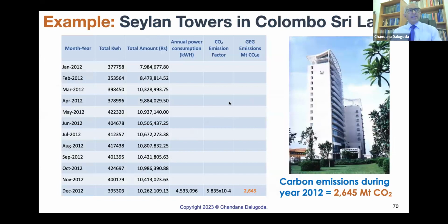Seylan Towers. You know where it is? Just opposite the Cinnamon hotels on Galle Road. Seylan Towers was built in 1994. It so happened I designed the system, and then it was installed by a Danish company. They had air-cooled chillers, and the efficiency, the highest efficiency during that time, was 0.83 kilowatt per ton. Actually, this is just after the twin buildings of the World Trade Center, and they had 0.83 kilowatt per ton. That is the highest efficiency during 1993 and '94.